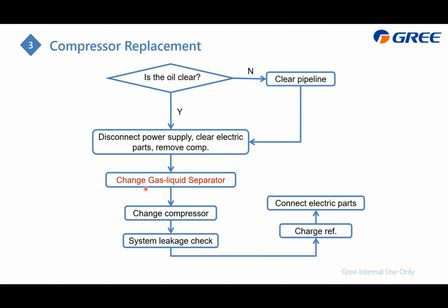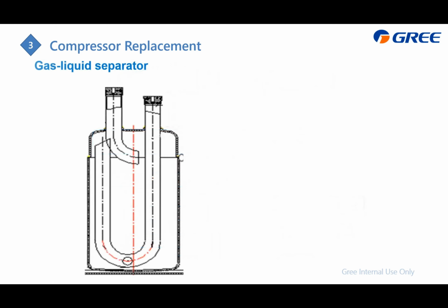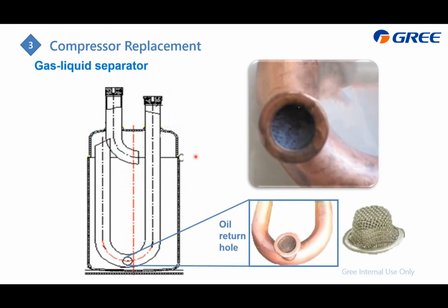The reason why we require this one is this. And this is the sectional view of this gas liquid separator. The refrigerant flows in from here, and the liquid part will accumulate here, and the gas part will flow in from this one and then to the compressor. And you can also find that there is a hole here with a filter. It is actually for the oil return, which means what we're afraid of is this: when we're going to replace the compressor, that means the compressor has probably burned down, right?